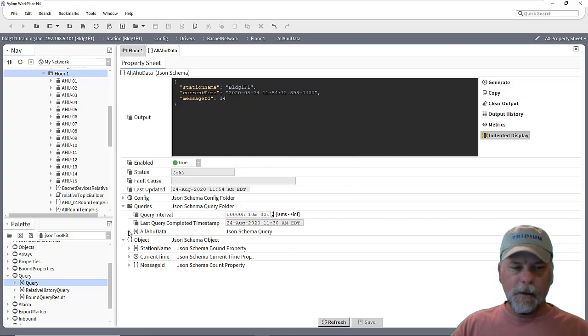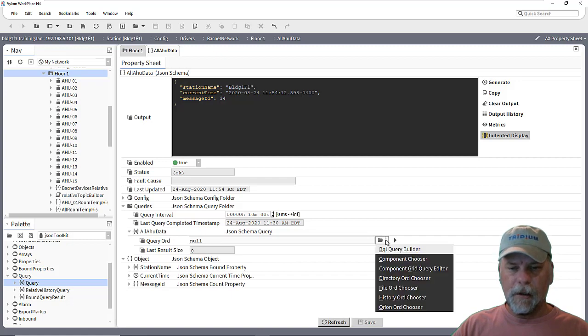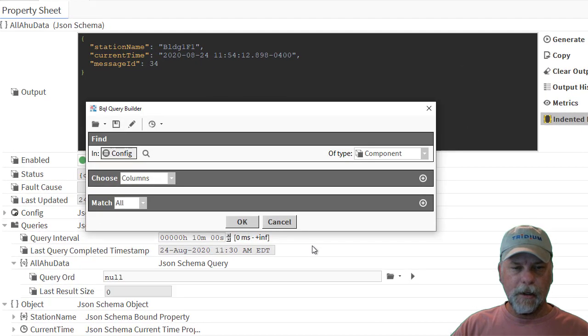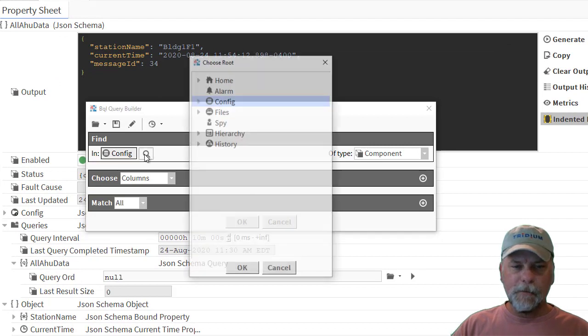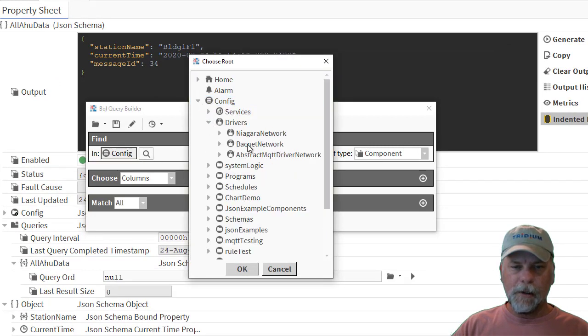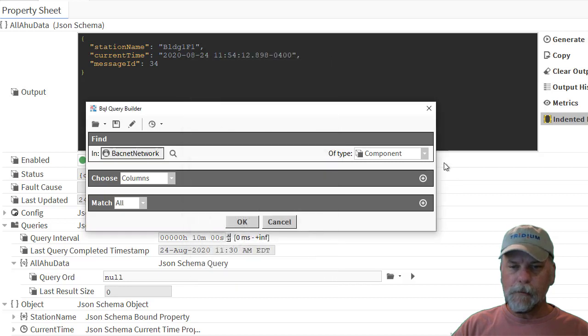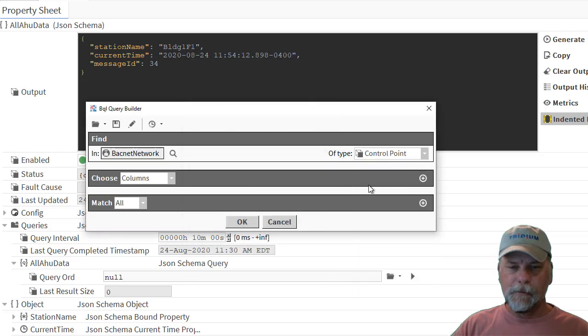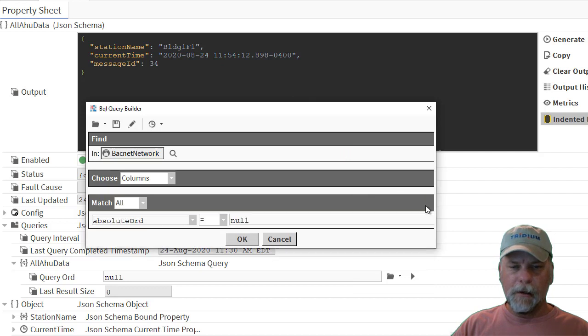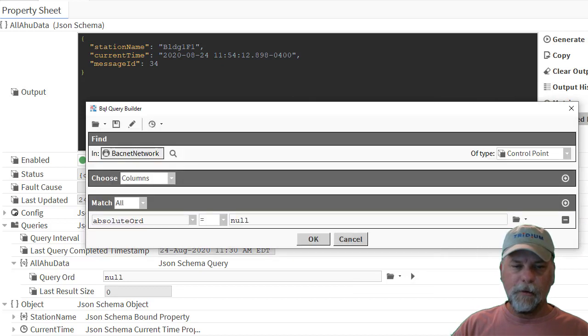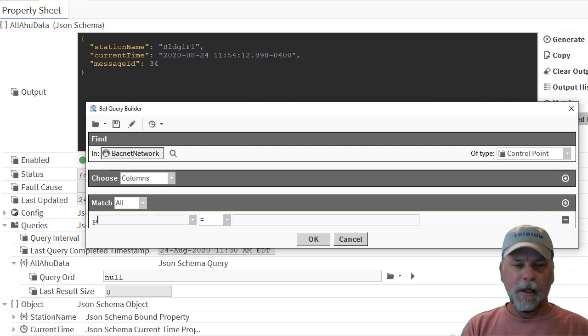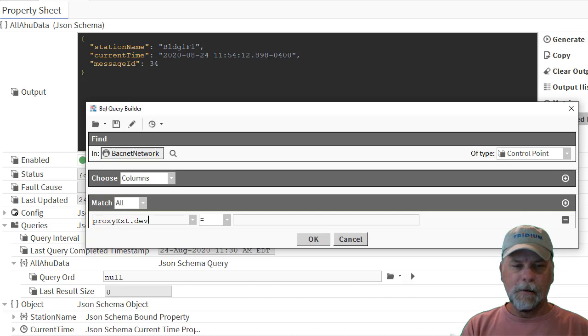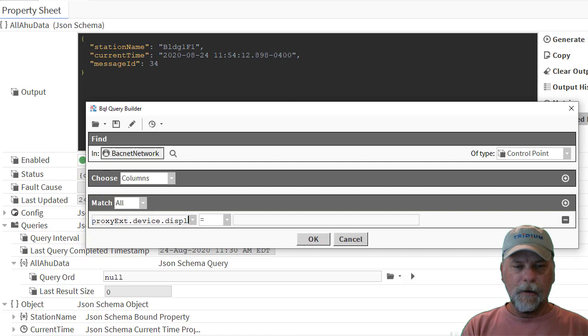And really, you can use your imagination here as far as setting up a query. It could be an equal query or be equal query, combination thereof. In this case, maybe I'll limit the scope of the BQL query to the BACnet network. And then look for control points. And we can use whatever sort of predicate that we want to here. Maybe I'll keep this somewhat simple and just say, you know, proxy extension device. So there's a get proxy extension, get device method, and then get the display name.